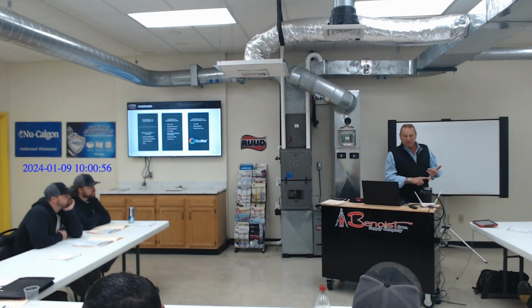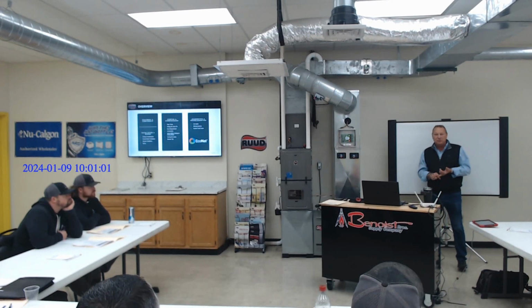In some cases, some of our matchups have an 85,000 furnace on a 3-ton air conditioner or 3.5-ton air conditioner to get your AHRI numbers. You need more airflow for that 85,000 furnace than you need for that 3-ton air conditioner, gentlemen. And we don't realize that, and we're in trouble. The only advantage I have with the 96 Vs and now the 96 2Vs is they're 2-stage. So I can keep them maybe locked down. I can lock them down to just stay in single stage. Because we're oversizing furnaces too, let's face it. We are all oversizing furnaces.